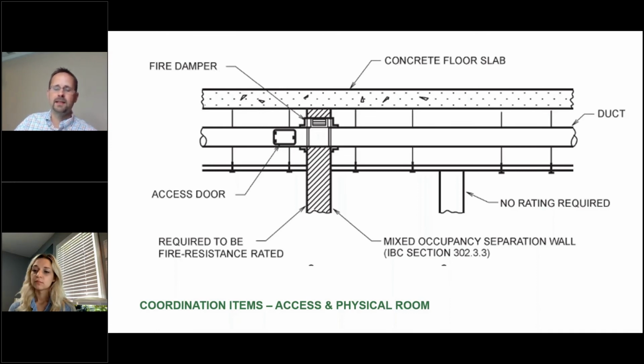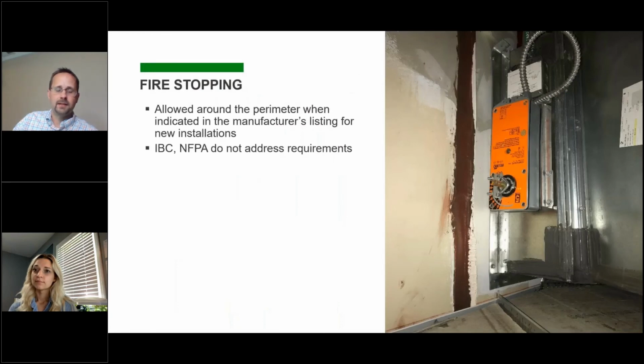Because even if it's in an area that's not required, they still have to do the same testing. So they have to fully decommission it so it can't operate anymore, and then put a label on it to say that it's no longer under commission. That's pretty much the extent of what we have.